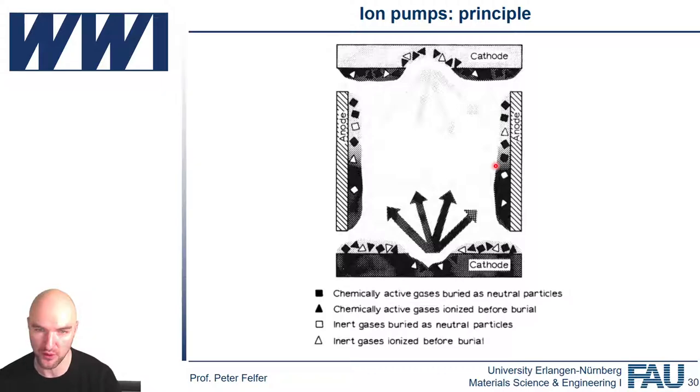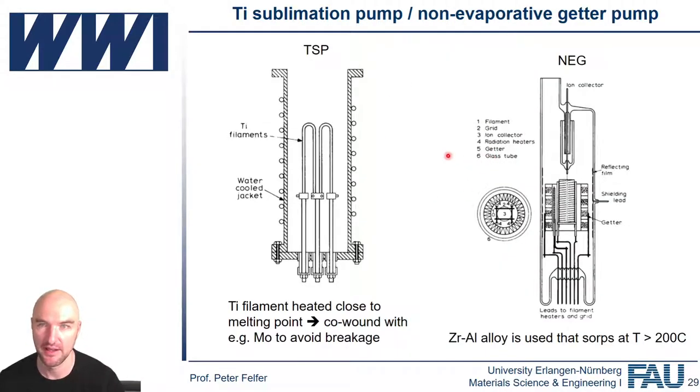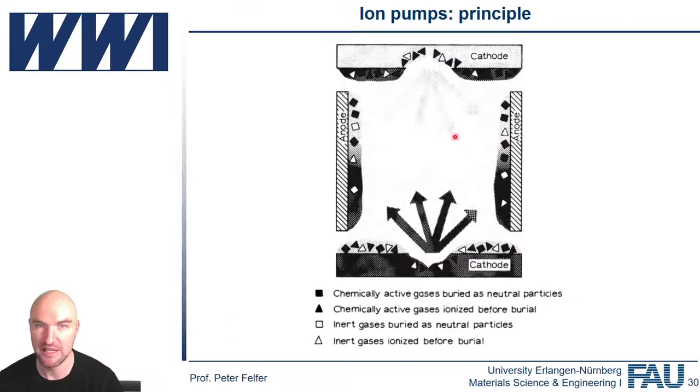So you've got twofold action. First of all, you bury your elements, so even non-reactive elements will be pumped, which in the other pumps you're not going to pump any non-reactive elements. So if you've got argon, helium, any non-reactive elements, no pumping action whatsoever. Here you've got some reasonable pumping action. And you always create fresh surface with some fresh metal that can also chemisorb material.